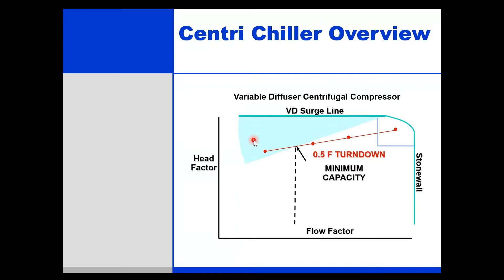I will talk about the inlet guide vane. Of course, we have discussed inlet guide vane, so I'll just quickly take you through. Inlet guide vane is a component which looks something like this. It is responsible for allowing the refrigerant to flow into the compressor. So this part that you see is responsible for allowing the refrigerant into the compressor, and it can open and it can close. And if you see, these are the ropes that are there, which is of course coupled with an actuator motor, which gets actuated, pulls the rope, and these ropes are tied with these lobes that you see in the inlet guide vane. It opens and closes.